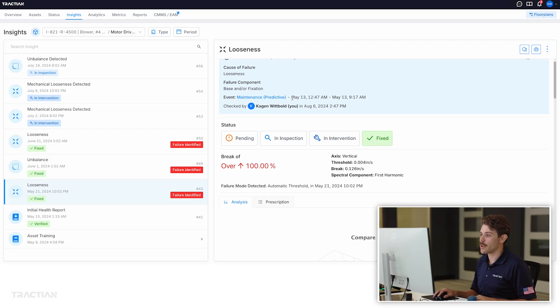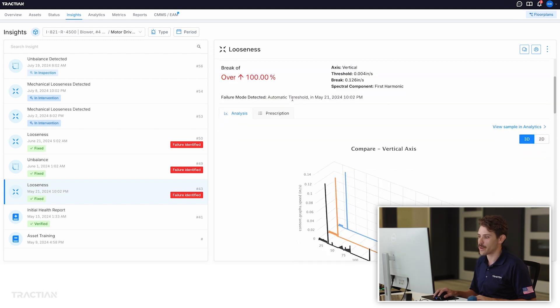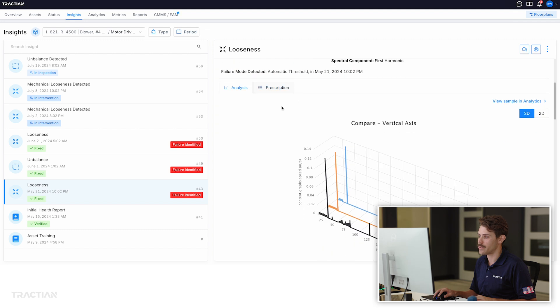We issued an insight on May 13th, nine days after we installed our sensors. We identified a high one-times running speed peak, which is shown here in this analytics sample. As a CAT-2 vibration analyst, we're looking for patterns that indicate specific failure modes of equipment. We issue prescriptive insights based off of these patterns — something that's been done through traditional vibration analysis for decades. What we're doing is applying an artificial intelligence algorithm to it, doing that kind of sampling thousands of times over a day.